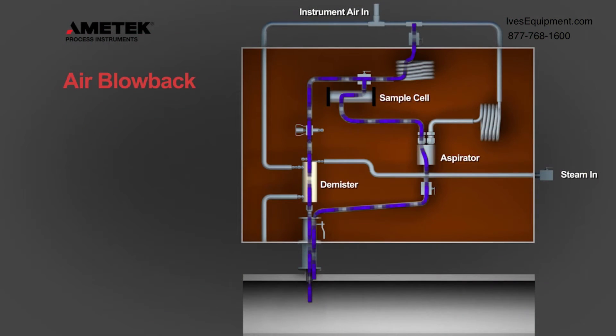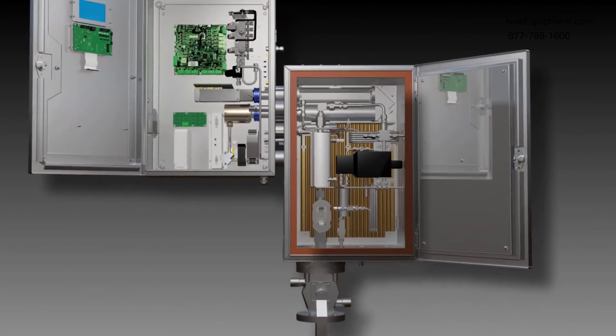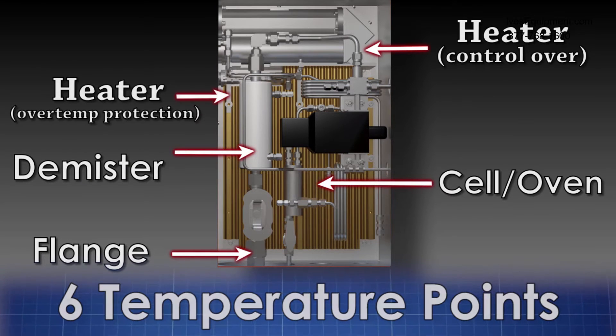The 888 is also equipped with an anti-clogging blowback feature that is automatically initiated if plugging is detected by the smart diagnostics. The advanced thermal management reduces the electronics enclosure's internal temperature, extending the life of the electronics by 75 percent.